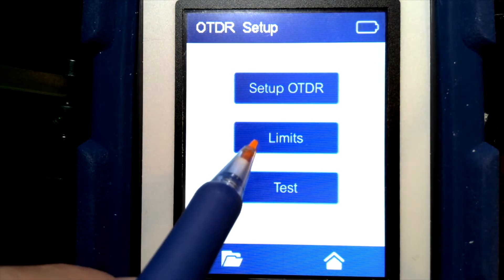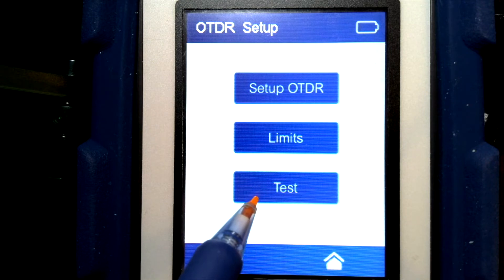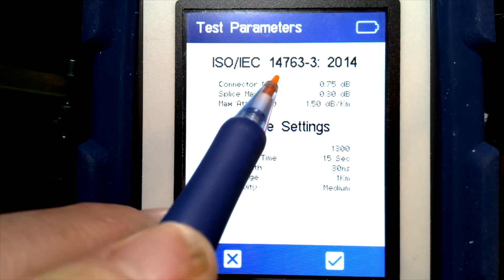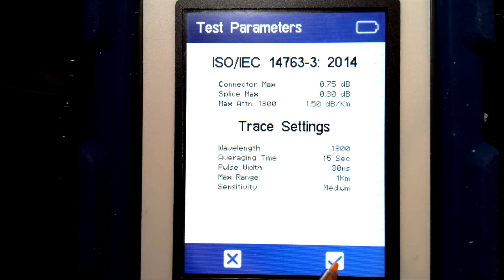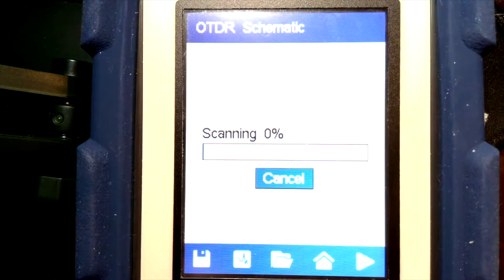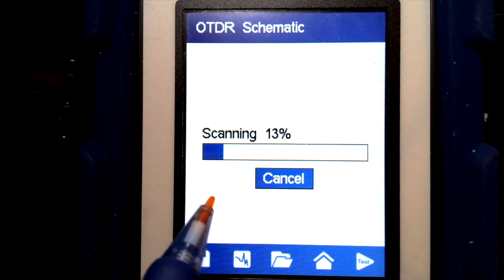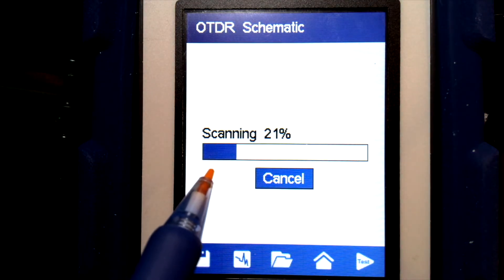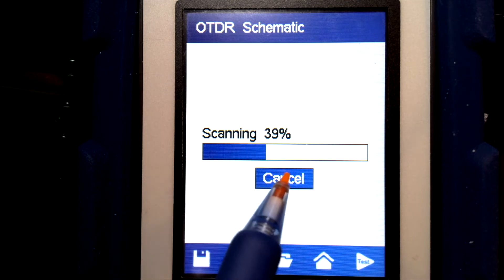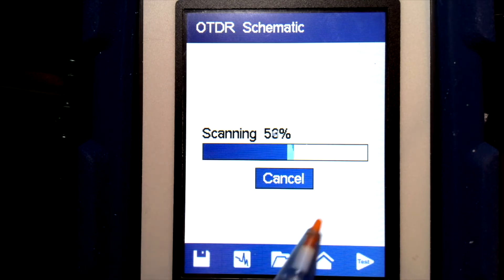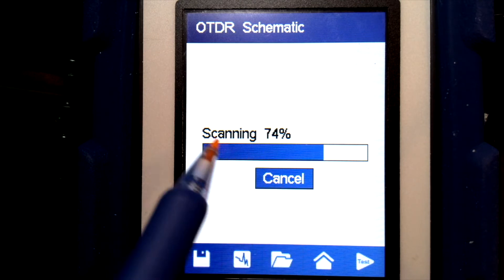We'll look at the limit configuration later, but right now let's just run a test and see what that looks like. This gives us a confirmation screen — we're happy with our settings and it'll start scanning. Each time it's testing, it's doing thousands of tests in this 15-second period and averaging all that information together to average out the noise.